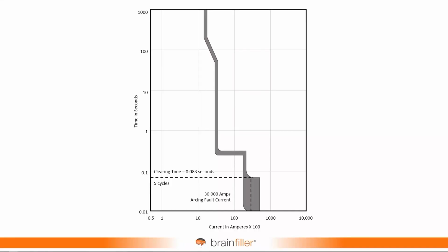So a case in point right here, let's say there's a location where there's 30,000 amps of arcing short circuit current. This time current characteristic indicates that this device should operate in 5 electrical cycles. I should note it's 5/60ths of a second because I know people from other parts of the world have 50 hertz systems. So 5 electrical cycles based on a 60 hertz system, that's 0.083 seconds. But if the fault current were to drop, maybe because a transformer is taken out of service. You have 2 transformers in parallel, and maybe one is taken out of service. The fault current drops. This device will now take a lot longer. And the arc duration has a very large impact on the incident energy.